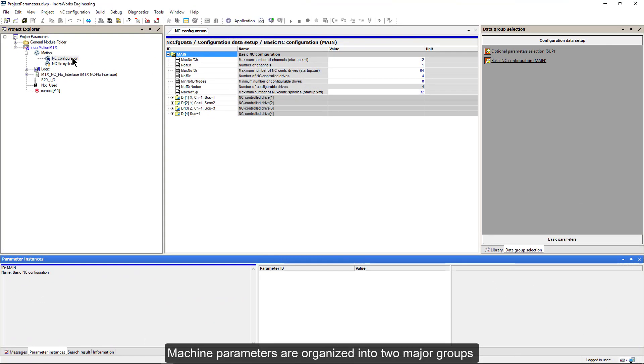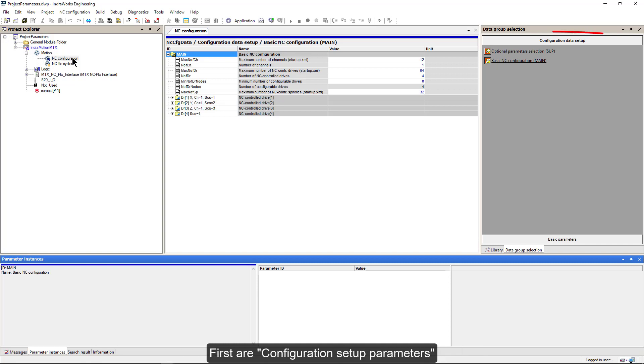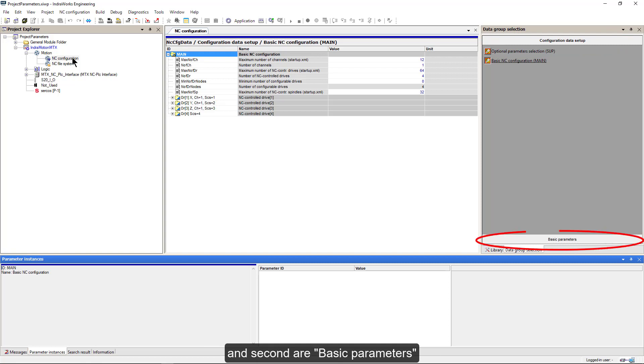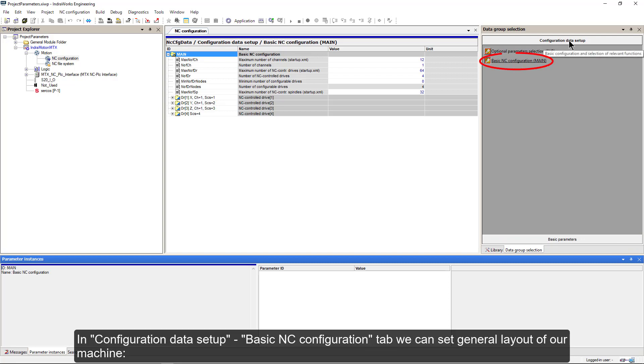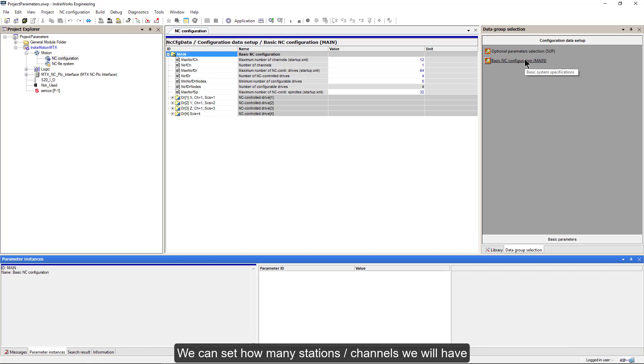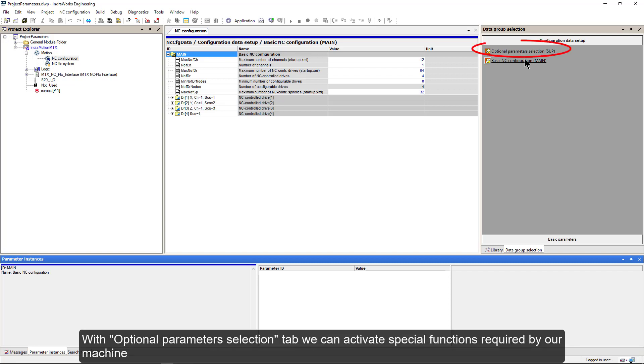Machine parameters are organized in two major groups. First are configuration setup parameters and second are basic parameters. In configuration data setup, basic NC configuration tab, we can set general layout of our machine. We can set how many stations and channels we will have and how many and what type of axes we will have. With optional parameter selection tab, we can activate special functions required by our machine.